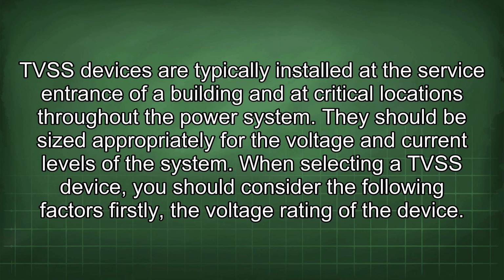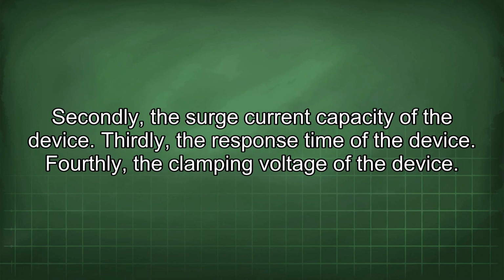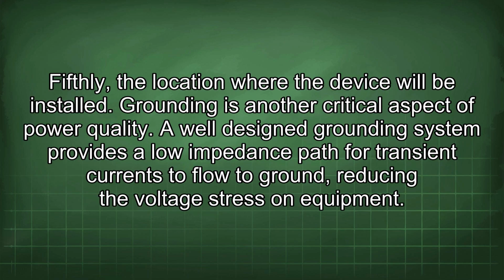They should be sized appropriately for the voltage and current levels of the system. When selecting a TVSS device, you should consider the following factors. Firstly, the voltage rating of the device. Secondly, the surge current capacity of the device. Thirdly, the response time of the device. Fourthly, the clamping voltage of the device. Fifthly, the location where the device will be installed.